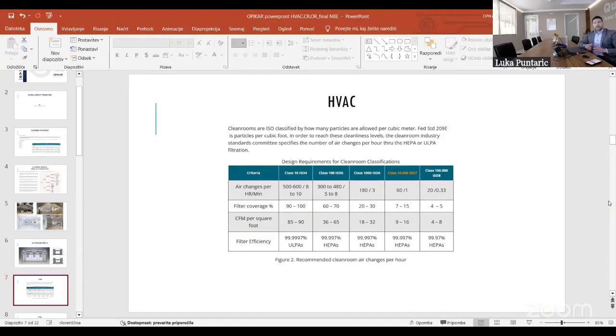And then we multiply this with 20 in the case of ISO 8 plus, and we get how much fresh air needs to be supplied by the air handling units to the room every hour, so many cubic meters. So this means, as we can see, there is a huge difference between ISO 8 and ISO 4 plus: 20 air change rates or 500 air change rates. It means even the HVAC system is a lot more complex in the case of a higher clean room class.